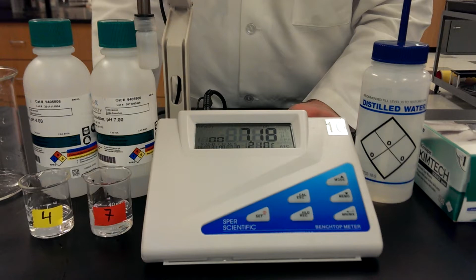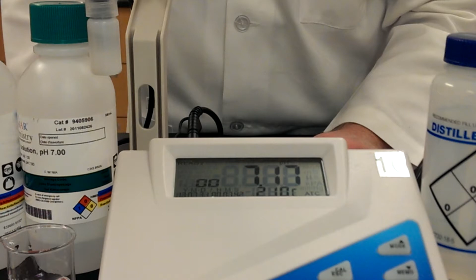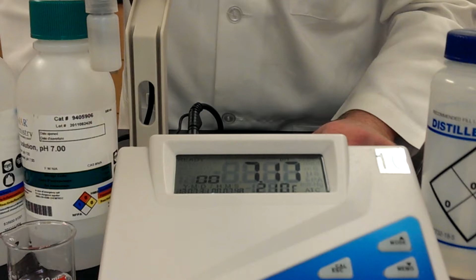So we're going to do some troubleshooting and see if we need to actually calibrate this pH meter, or if the solution in here is just not a pH 7 buffer, which is also possible. Sometimes that can happen because students who use this pH meter before you do not rinse and put pH 7 buffer into the cap correctly after they use it, and that messes up the pH reading that you see initially. So we're going to do some troubleshooting.